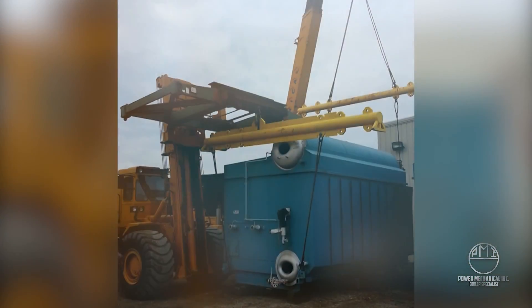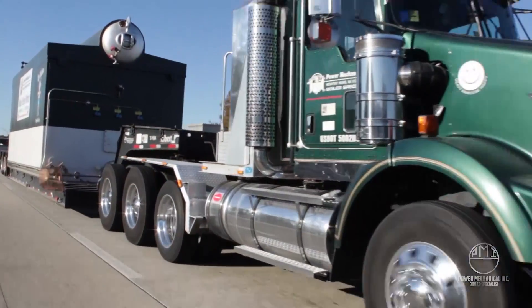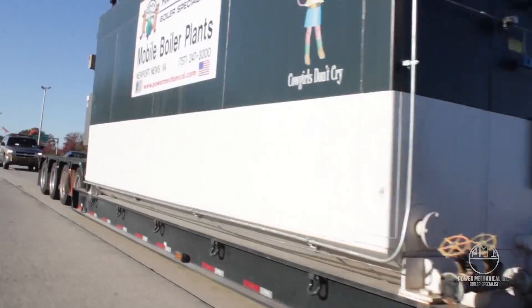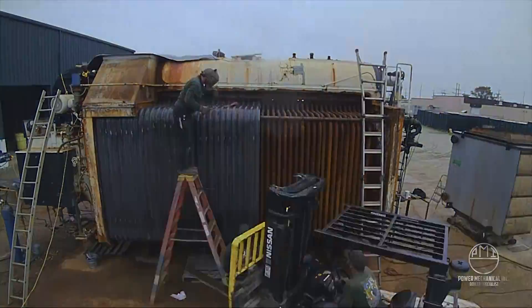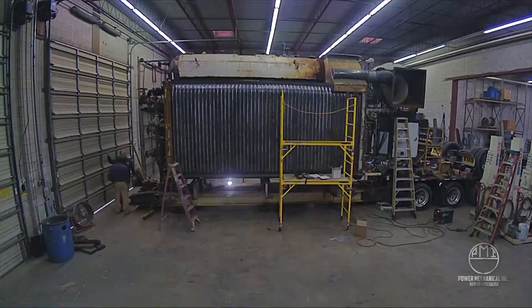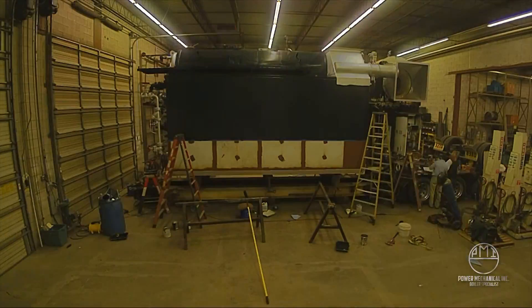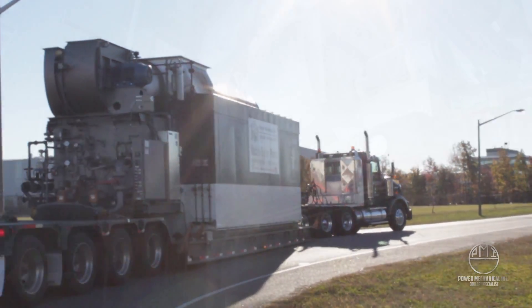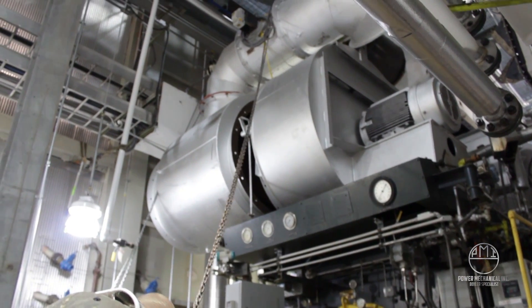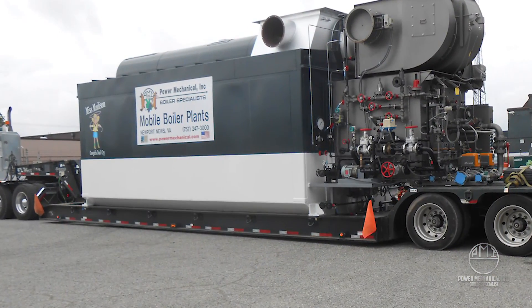These boilers will oftentimes have much larger upfront costs; however, due to their efficiency ratings, they generally are a lower cost to operate over time. The design and size of the water tubes do present a bit more complexity with cleaning and other maintenance procedures as compared to the fire tube's compact design. A retubing procedure of these type boilers is practically a complete disassembly. With industrial and manufacturing demands worldwide for high-pressure steam, the water tube boiler towers over other designs in size and performance.